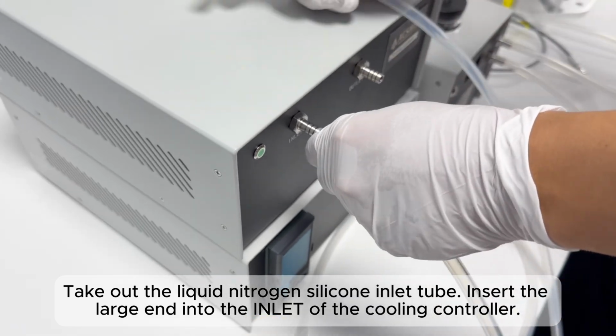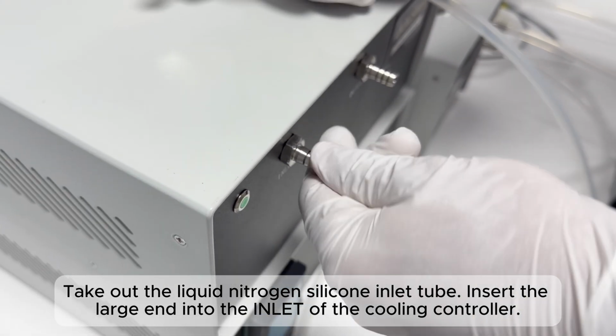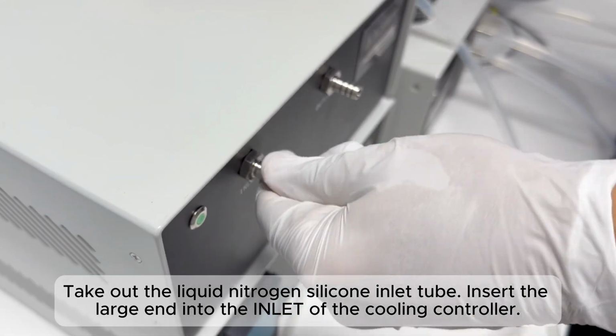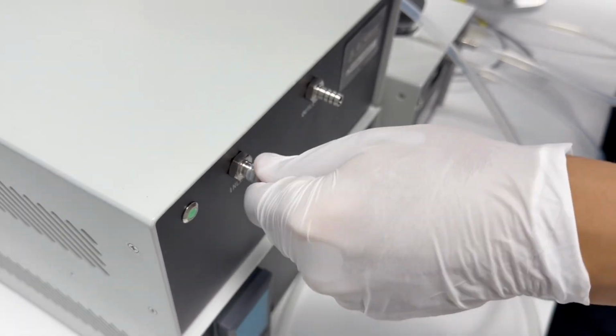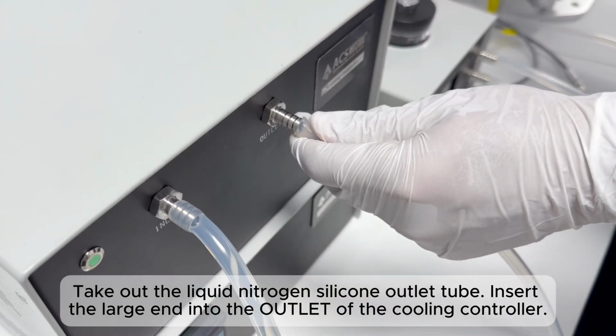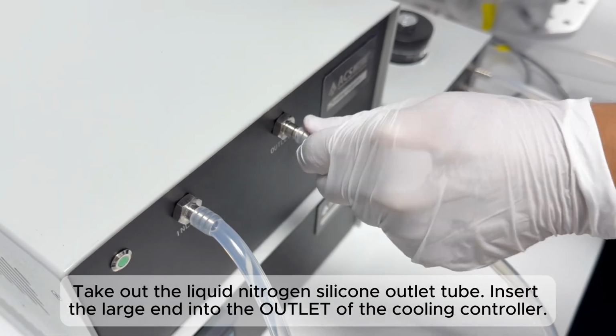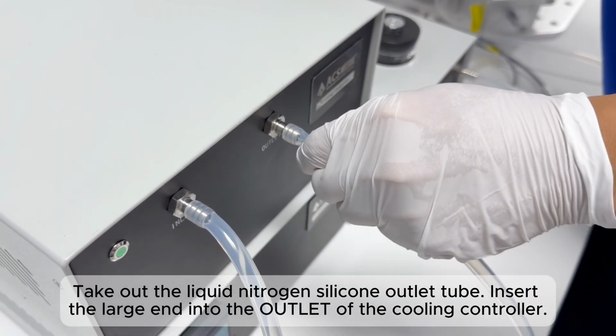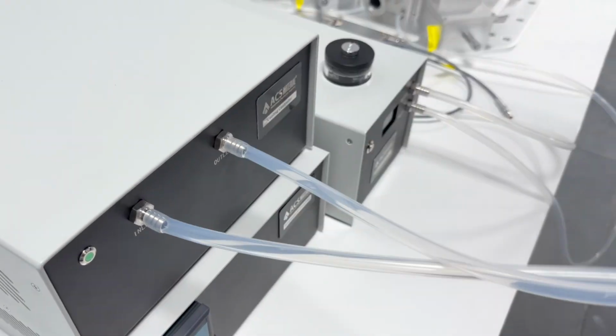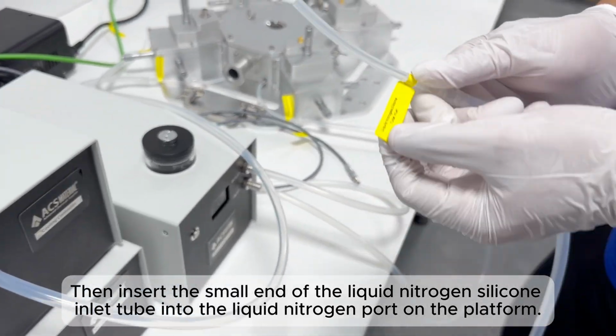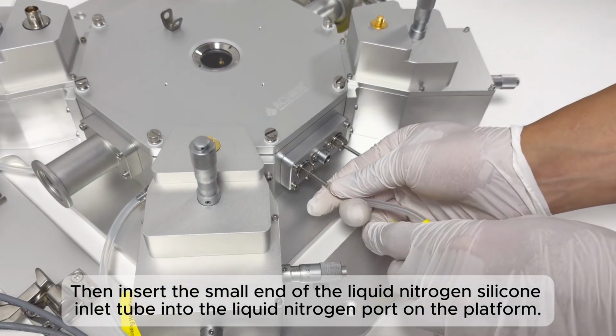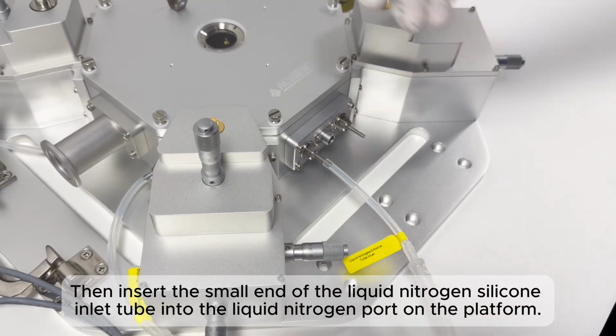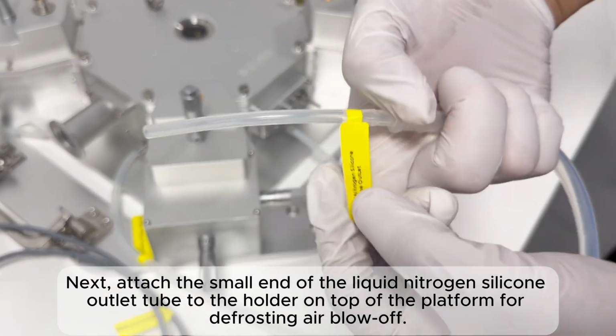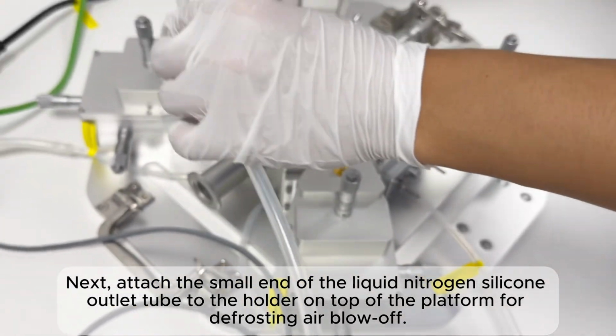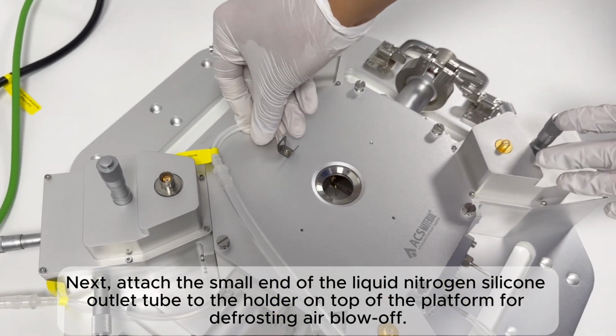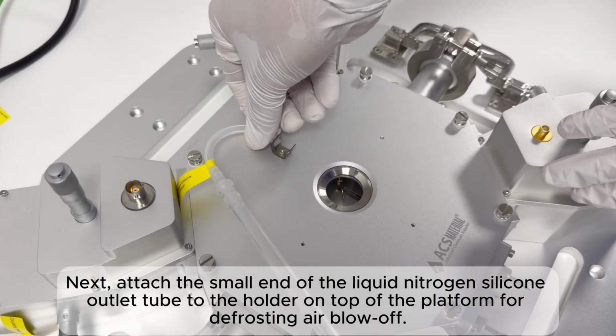Take out the liquid nitrogen silicone inlet tube. Insert the large end into the inlet of the cooling controller. Take out the liquid nitrogen silicone outlet tube. Insert the large end into the outlet of the cooling controller. Then insert the small end of the liquid nitrogen silicone inlet tube into the liquid nitrogen port on the platform. Next, attach the small end of the liquid nitrogen silicone outlet tube to the holder on top of the platform for defrosting air blow-off.